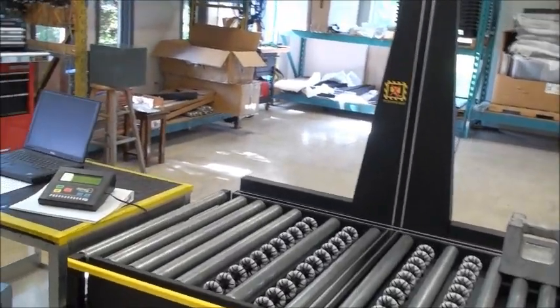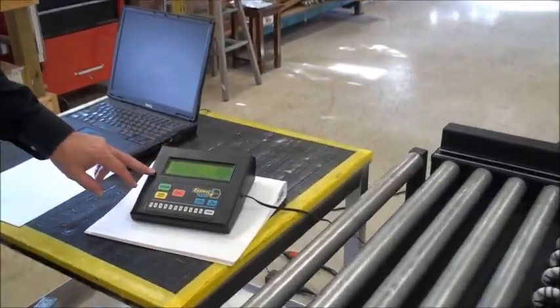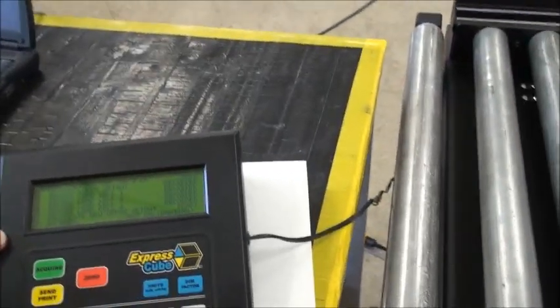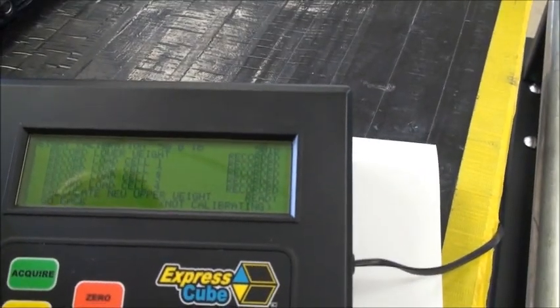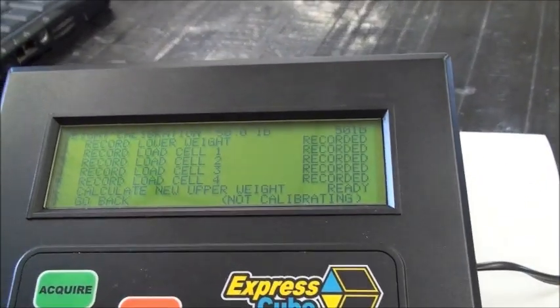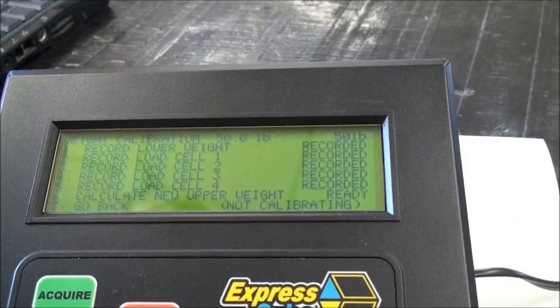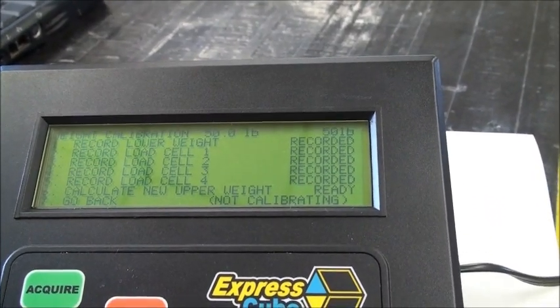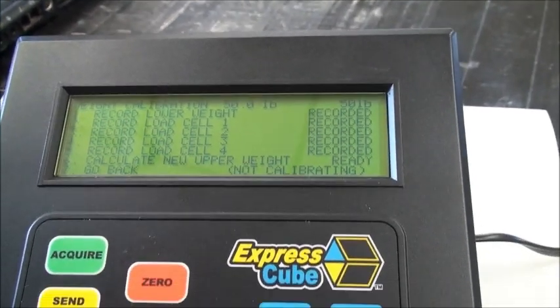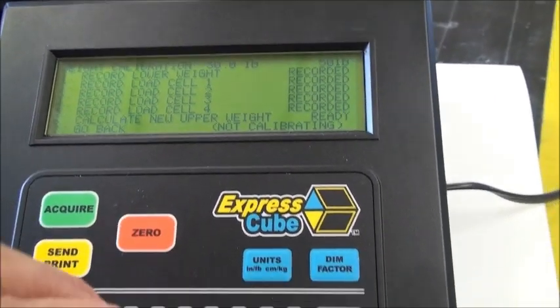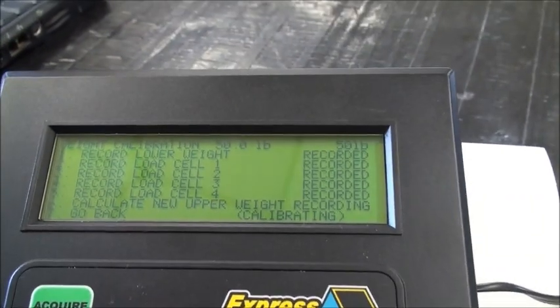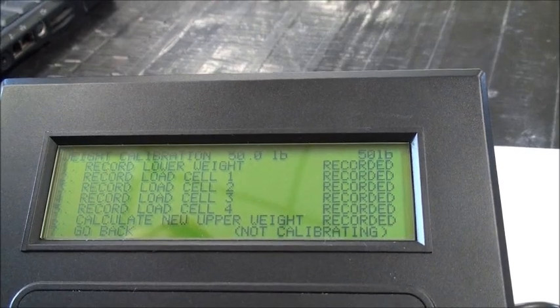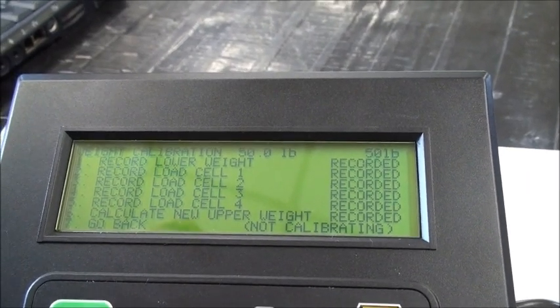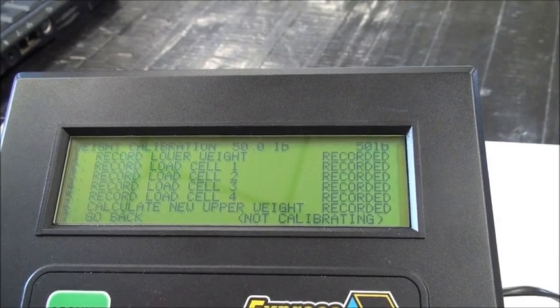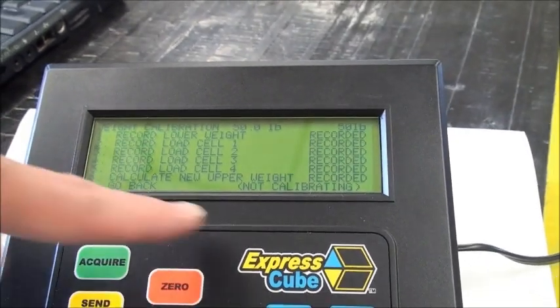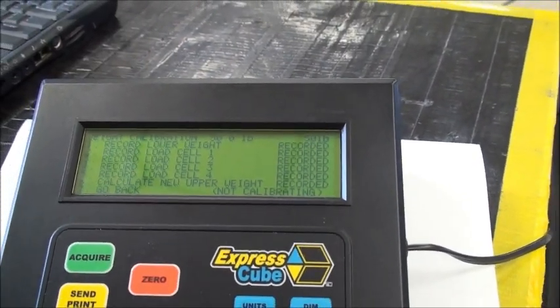Now it's recorded. Now, the last thing I have to do: it has now taken a new reference for all the load cells, and it's going to calculate the weight based on those load cells. So I press number 6, which is calculate new upper weight. So what it's doing now is taking every load cell's characteristics, and it's now done. So it's finished doing it. You'll see recorded all the way up here.